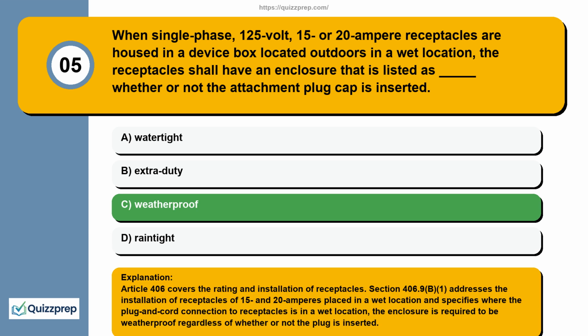Article 406 covers the rating and installation of receptacles. Section 406.9(B)(1) addresses the installation of receptacles of 15 and 20 amperes placed in a wet location and specifies where the plug and cord connection to receptacles is in a wet location, the enclosure is required to be weatherproof regardless of whether or not the plug is inserted.